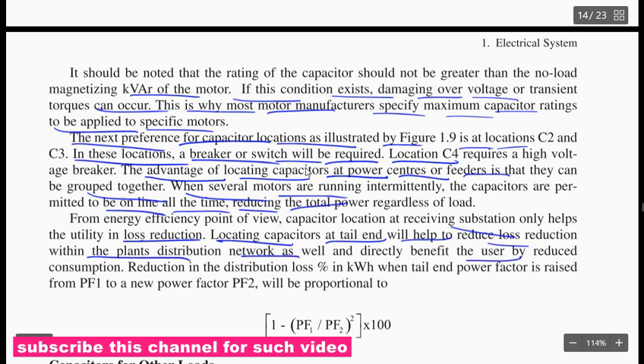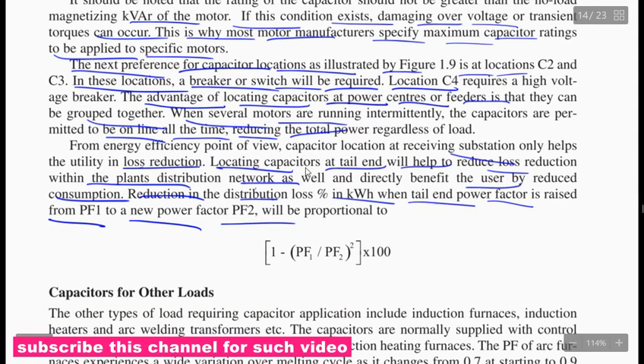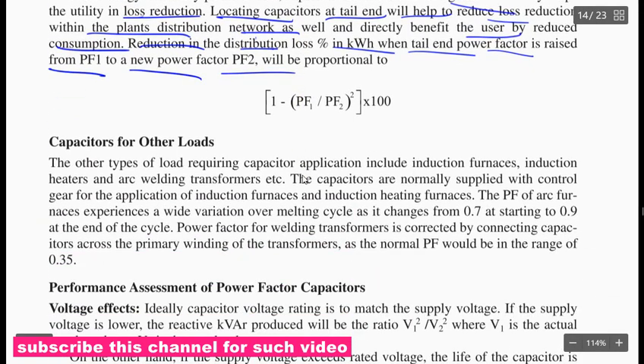directly benefit the user by reducing consumers' reduction in the distribution losses. kW savings when tail end user power factor is raised from PF1 to PF2 is proportional to 1 minus (power factor 1 divided by power factor 2) the whole square, into 100.